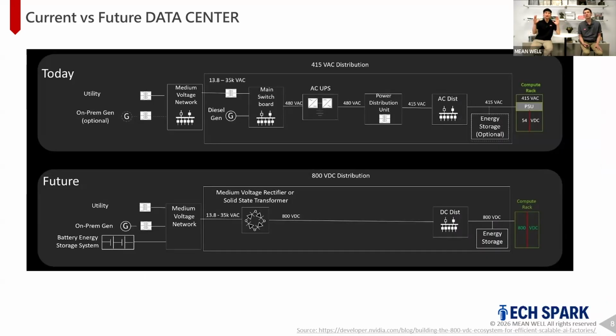Just to simplify this chart, the AC system essentially takes utility power, which is very, very high—13 to 35 kilovolts AC. There's a transformer in between that steps it down from that utility level power to 480, and then there's a separate AC distribution panel that steps it down from 480 to something more workable, like 55, which would eventually go on to power the servers.